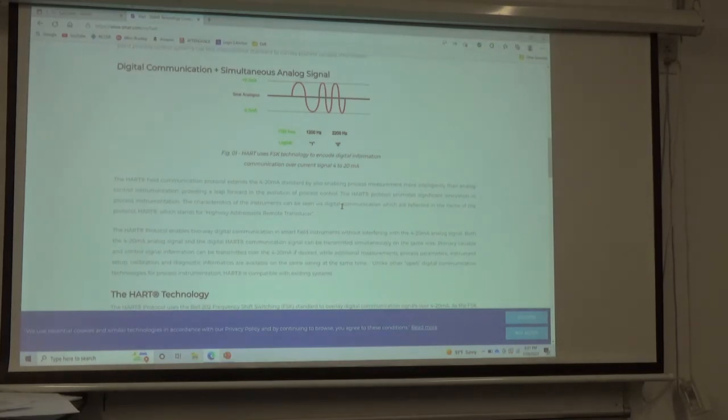Okay? So when you have a HART communicator, and that HART communicator tells you that my transmitter is reading 17 milliamps, that's not a 17 milliamp signal for sure. In order to be sure if it's a 17 milliamp, you need to use a digital multimeter or an ammeter. Because I'm going to show you later on in the class, when we get on transmitters, how that milliamp signal from that transmitter has to be calibrated. It can be sitting at 15, but the digital signal may say 16. So you have to calibrate that signal too. And I'm going to show you guys how to do all that.